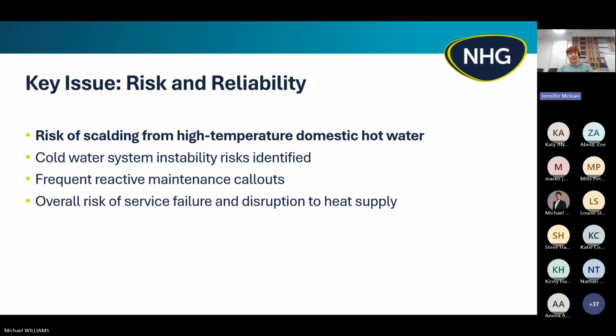So other key issues that were identified were obviously risk of scalding from high temperatures. The domestic hot water temperatures were recorded as high. The cold water system was unstable, and there were frequent reactive maintenance call-outs. I think we had a maintenance rate of 1 in 6 HIUs requiring regular attendance, and obviously a lot of those HIUs were bypassing, as mentioned earlier. So overall, there was a risk of service failure and significant disruption to the heat supply for residents. Next slide, please.